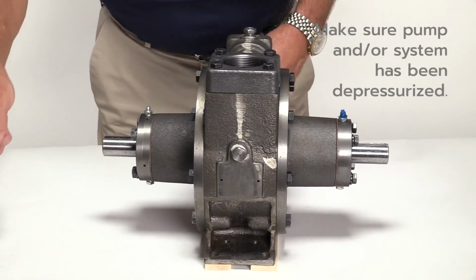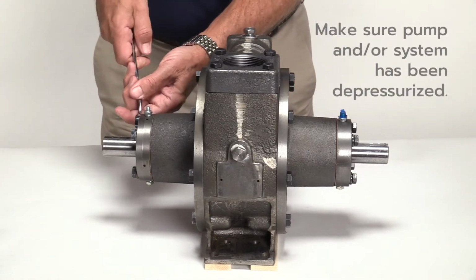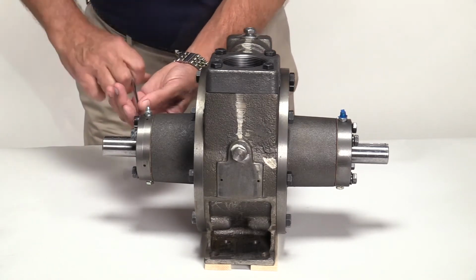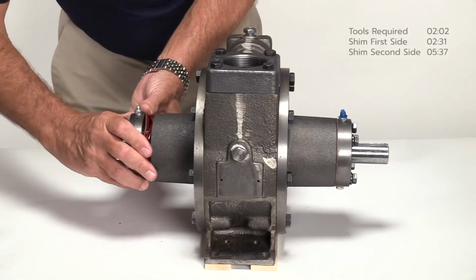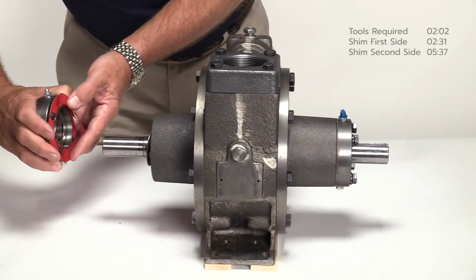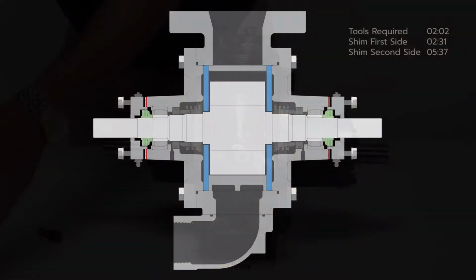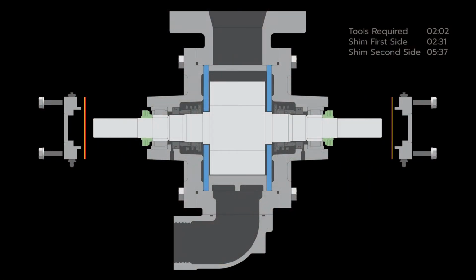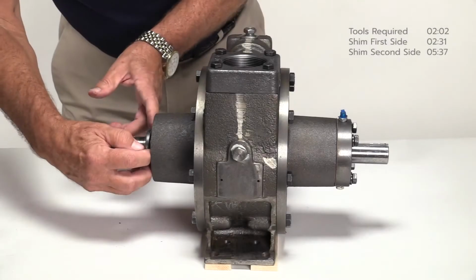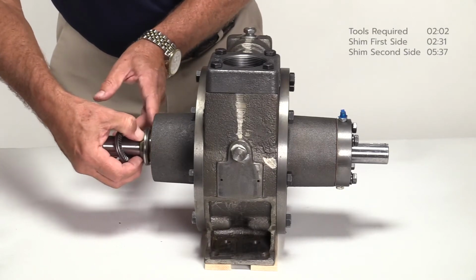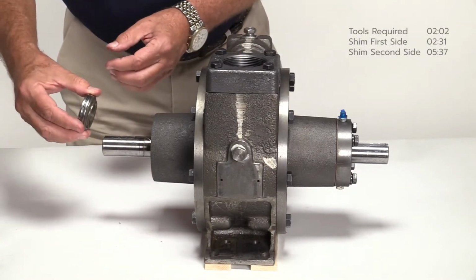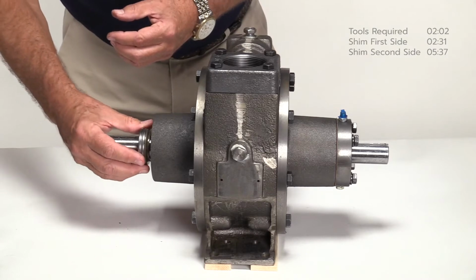Since this pump is fully assembled, begin by removing the bearing caps and existing shims from each side of the pump. Note the quantity and color of shims being used on each side. Remember, when installing a repair kit, reshimming is not typically required. Make sure the thrust bearings and mounting rings remain on both sides of the shaft and inside the pump covers as shown.